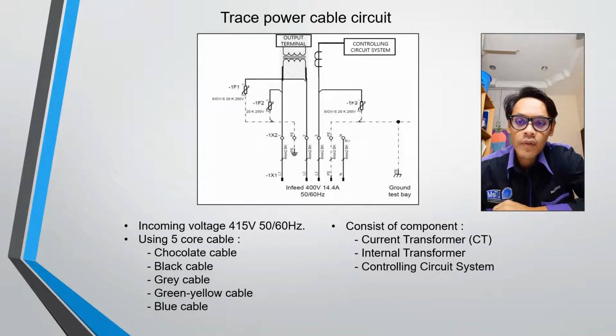From the internal transformers, the 2-phase cable will go to the terminal output of the frequency converter, where it will supply the voltage from 0 volt until 400 volt and connect to the primary side of the external transformers. The ground of the test bay must always be connected for safety purposes for those using this kit. That's all from me, and next time it will be continued by my group member YONG. Thank you.